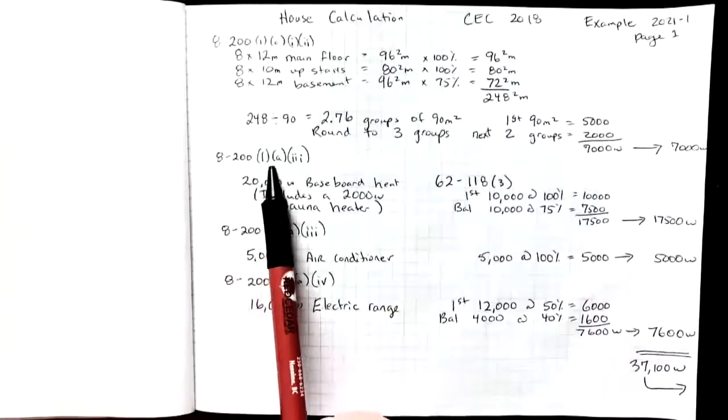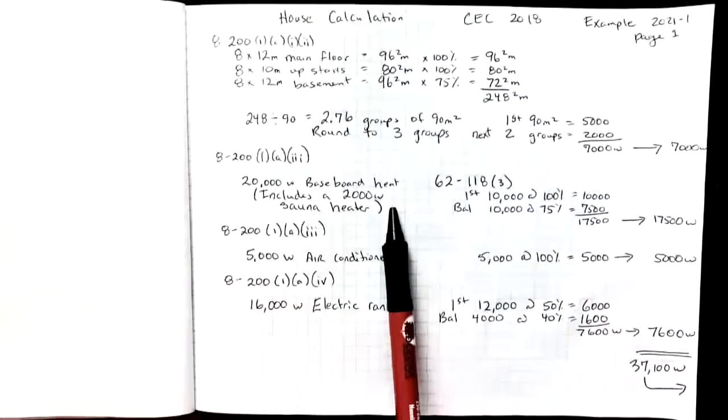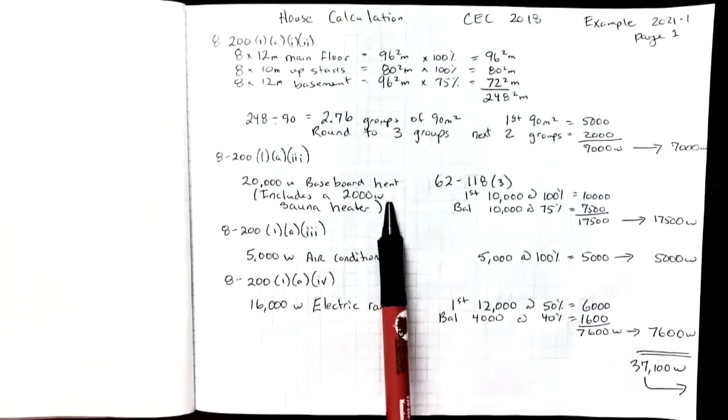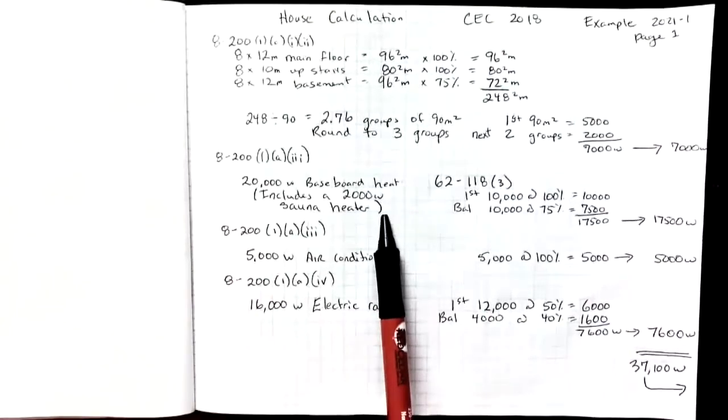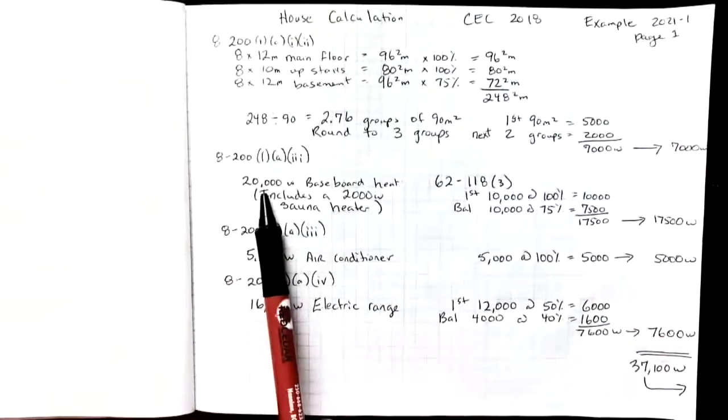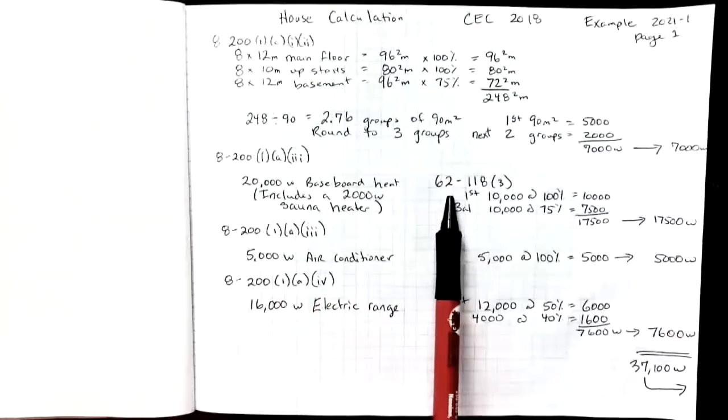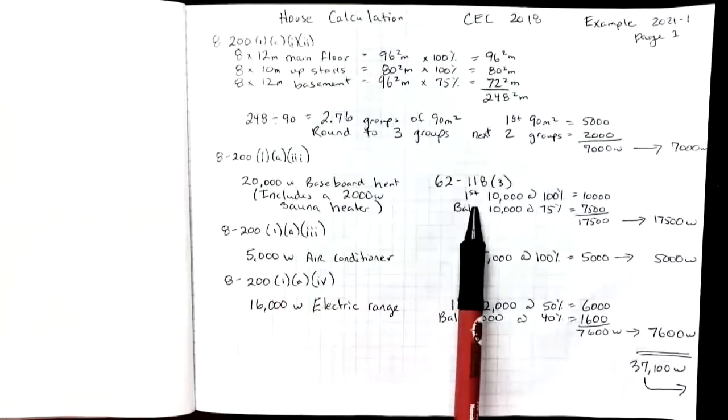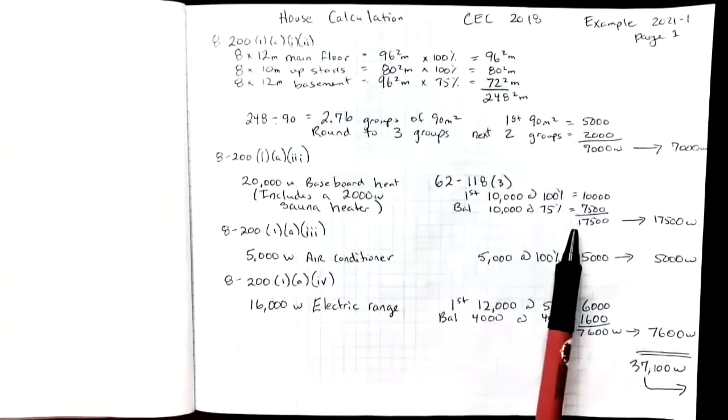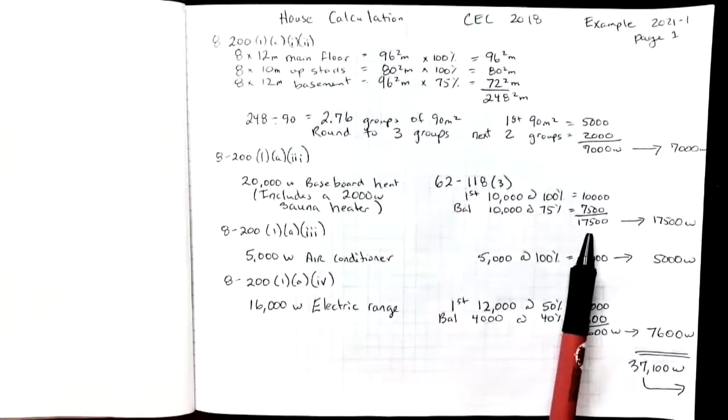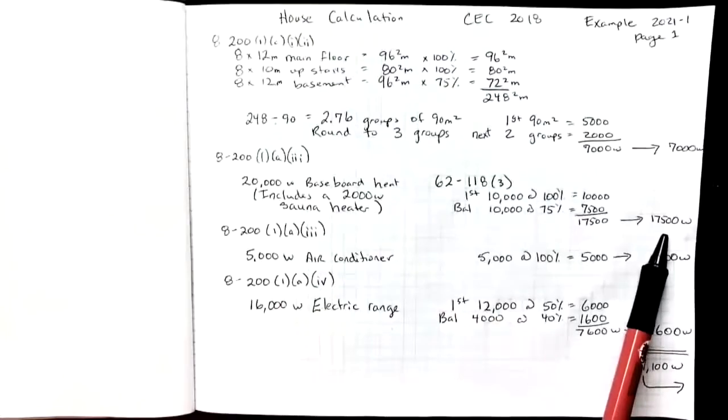Rule 8-200(1)(a) item 3 sends us to rule 62-118(3) for the baseboard heat. Remember that baseboard heat would include a heater in your sauna. In this case I had 20,000 watts total baseboard heat. When I go to 62-118 it tells me to take the first 10,000 at 100% and the balance at 75%. This would leave me with a demand for baseboard heat at 17,500 which I'm going to take towards the main service.